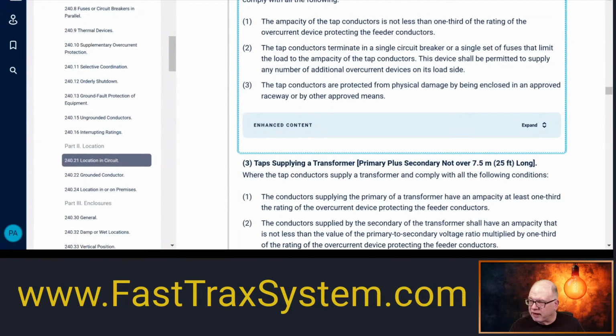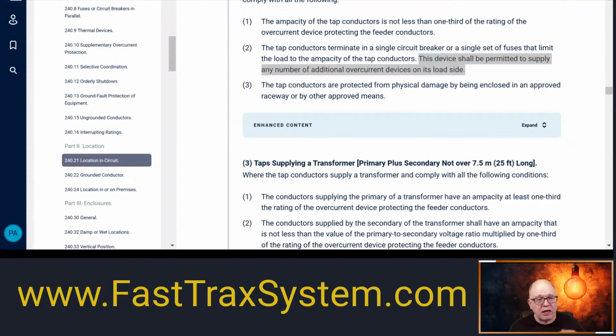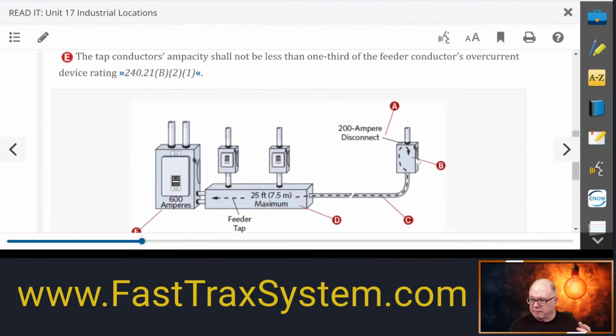Now it says this device shall be permitted to supply any number of additional overcurrent devices on its load side. This is what a lot of people do with these tap rules. The rule for this 25 foot tap is that it has to terminate into a single overcurrent device or single set of fuses, but you're thinking, I want to put more breakers in there, I want more loads handled by this. What's the deal? Well, it's okay as long as it terminates into that single device. It could be a panel board with multiple breakers in it, but you're hitting a main, whether circuit breaker or fuses. Or you could be hitting a disconnect, and then on the load side it's hitting a main lug only panel that's got a whole bunch of breakers in it. It's a design thing. However you want to design it.